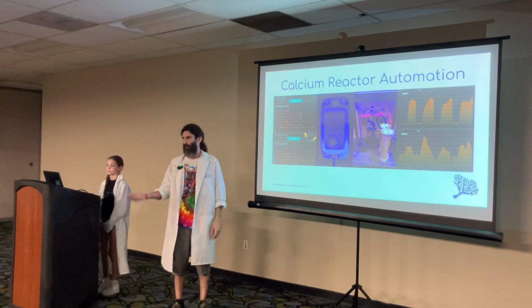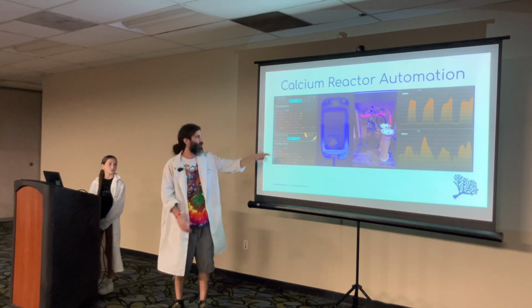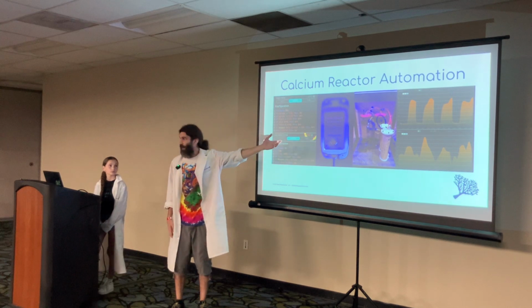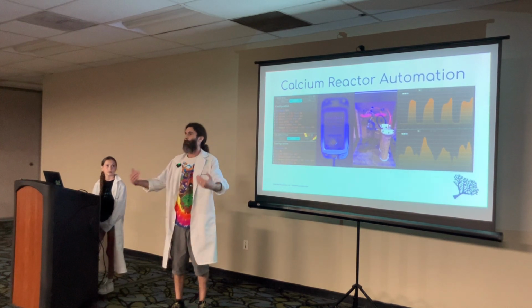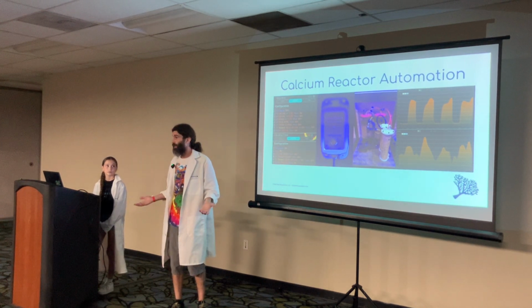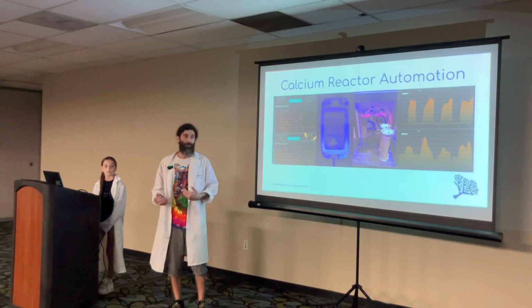So every 4 hours we're doing an alkalinity test, and we compare that in this code. If it's above 8.5, it shuts off the CO2 so we're not pumping anything else in, because we don't need any more alkalinity in the system. So we're regulating based on that.